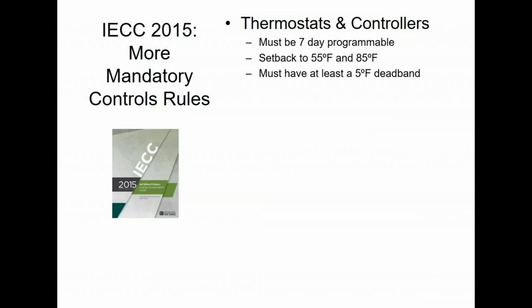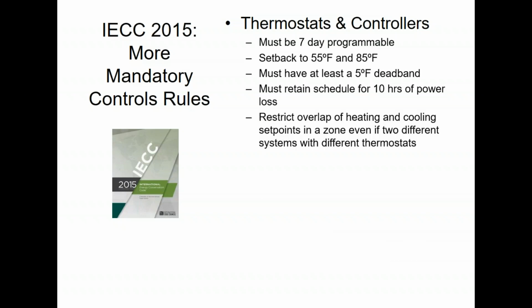Got to have at least a 5-degree deadband. That means there must be a minimum of 5 degrees enforced between the heating and cooling set points at all times. So if your cooling set point is 75, your heating can be no higher than 70, right? You can't have 70 for heat and 72 for cooling. That would not be allowed. 5-degree deadband between the heating and cooling. It's got to maintain power, or schedule on power loss. You cannot have overlapping heating and cooling set points, sometimes referred to as inverted set points.